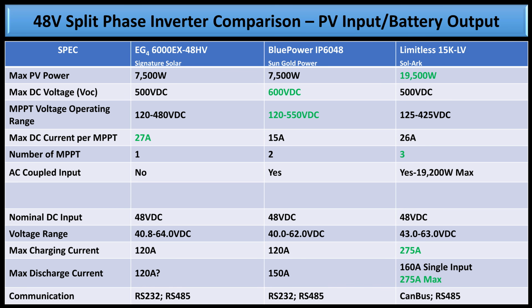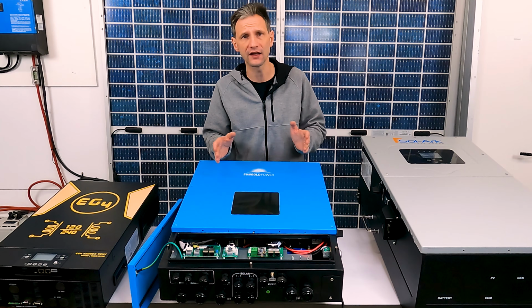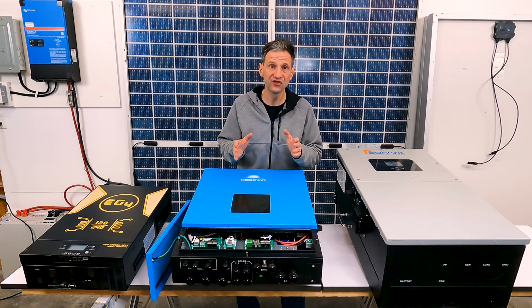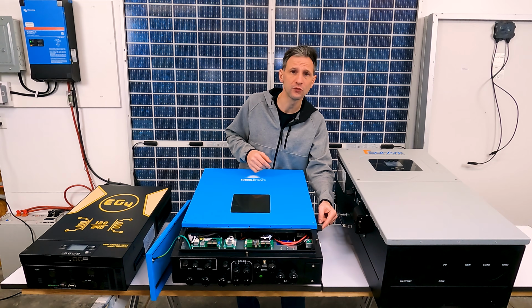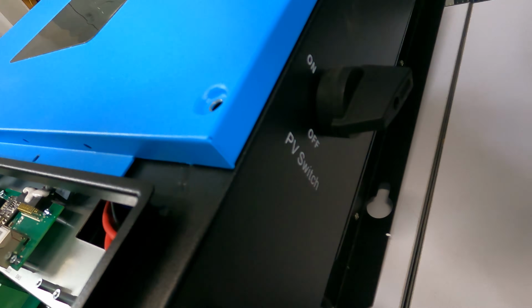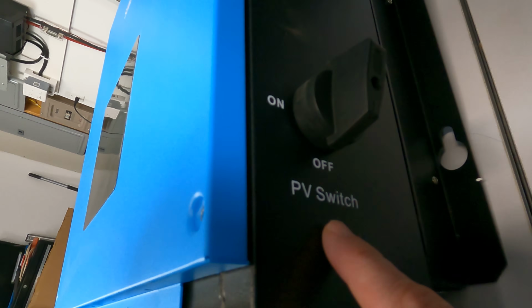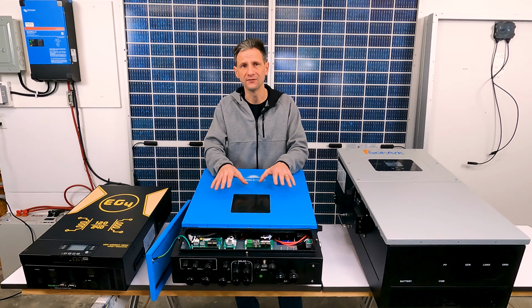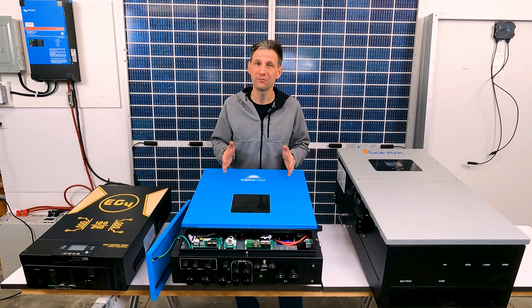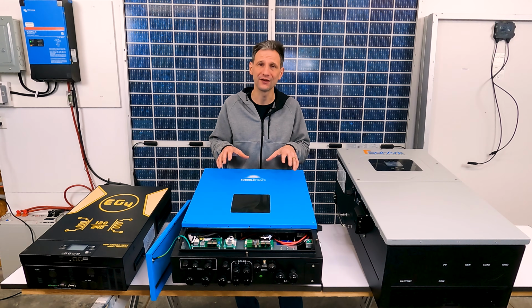This unit can provide a respectable 120 amps of charging current and up to 150 amps of discharge current. It has an RS-485 port for connecting to the battery BMS for automatic management and tracking of battery capacity. This unit has a built-in DC switch for the PV input, but you need external breakers for the AC connections as there are none built in. This is another great package at a very low price.